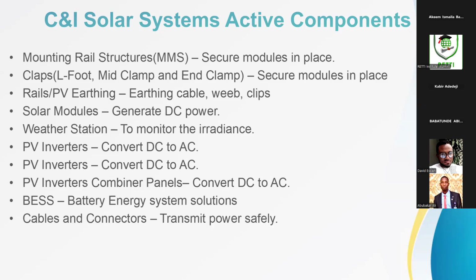So we have the cable and the connector transmitting power safely. There are so many sizes of cable. For the PV inverter, based on the size of the PV inverter, you need to size the cable that goes from your PV inverter to the PV combiner panel. Then the aggregate of the PV combiner panel going to the coma, or whichever controller you want to use, you also size accordingly.